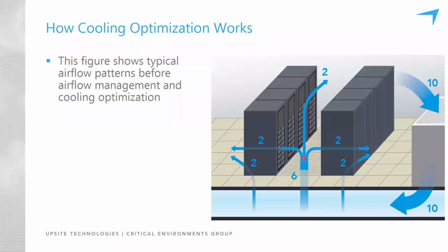When you look at the rows and the IT equipment contained in those cabinets, each row requires 2 units of air. So there's a total of 4 units of conditioned air required by the IT equipment. And this is a statement you don't hear very often: the amount of air moving through the IT equipment is completely independent of the amount of air moving through the cooling units or moving through the room.